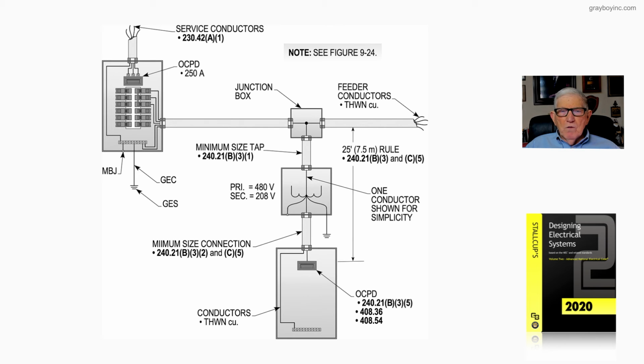Now notice the overcurrent device on the secondary side in the panel board has to comply with 240.21(B)(3), item 5, and 408.36 mainly. And then, of course, we have a minimum size tap that would be selected for the primary from 240.21(B)(3), item 2, where we make connections, and C5 of 240.